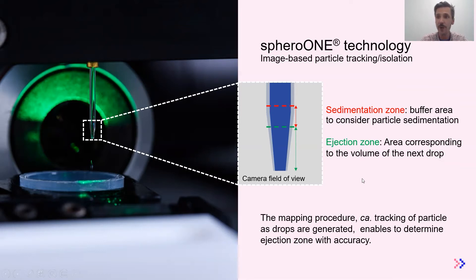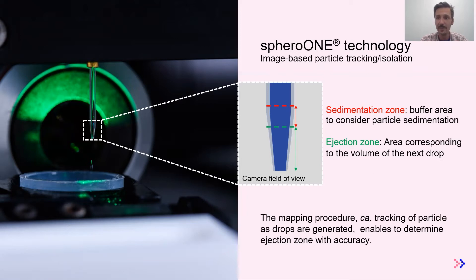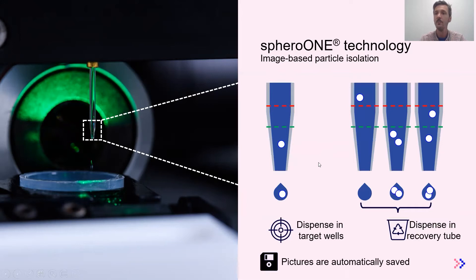This is also useful to track particles inside the capillary, which we use during a procedure called mapping to accurately determine the zone we call the ejection zone, which corresponds to the volume of the next drop. On top of that, we add the sedimentation zone, which is a buffer area used to account for sedimentation that may occur inside the capillary. Before making a single drop, the software can take an image and analyze it.